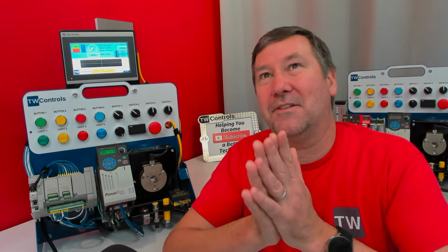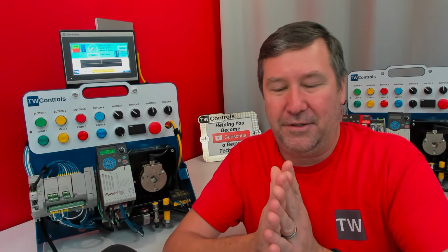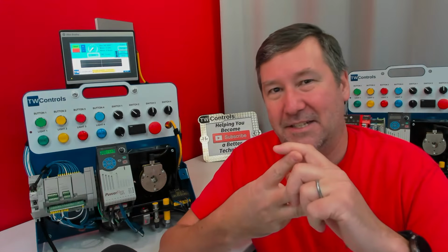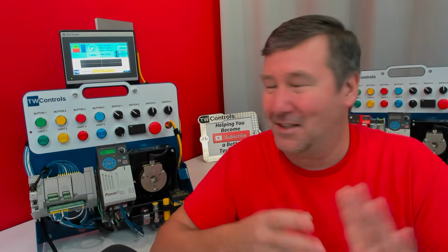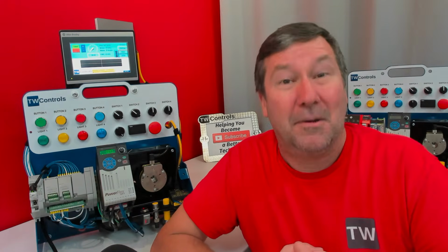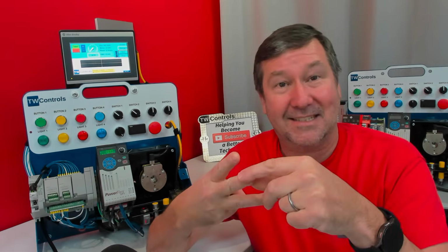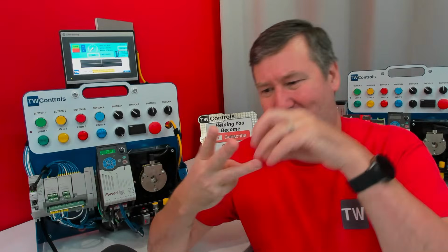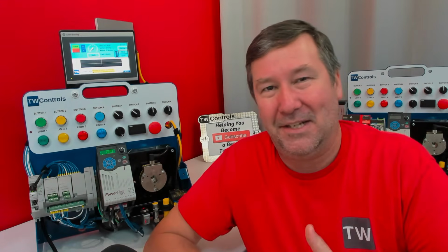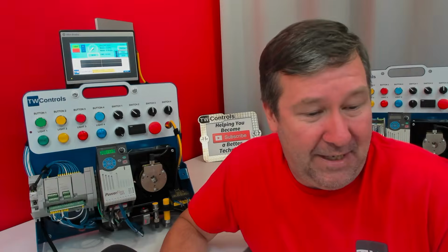So it's funny, I don't think it matters which HMI or SCADA software you're using. I think there are still three basic things you need to do. Now, from an HMI SCADA standpoint, a lot of you data people out there are like, oh, there's a lot more to it than that. But if we want to build a screen, we need to configure communications, tags, and then our graphical interface. And we always want to start right out of that graphical interface. But if we do the other two first, life will be much smoother.